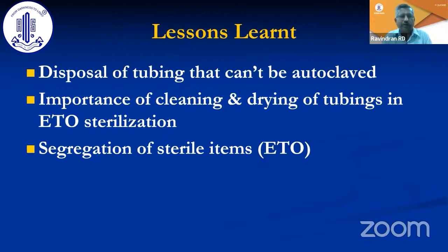That is also the point when we stopped reusing disposable tubings that cannot be autoclaved. Wherever we were using reusable tubing that can be autoclaved, we used them. If it has to be ETO'd, then we gave it away. We also understood the importance of cleaning and drying of the tubings. Still, some retina tubing reusables are used, so we really make sure that people are well trained to do this part.